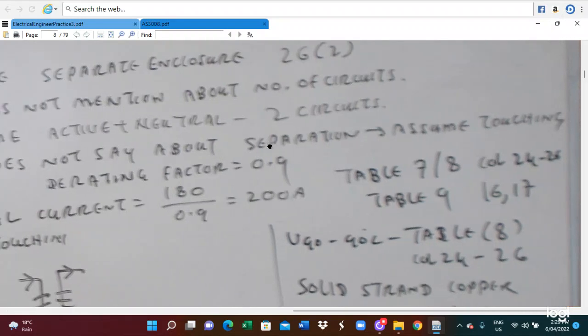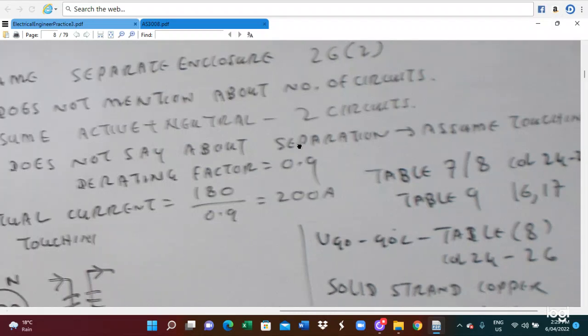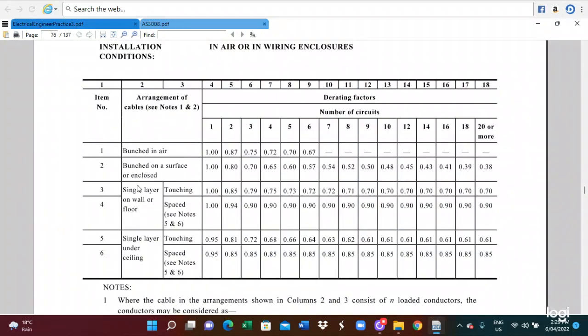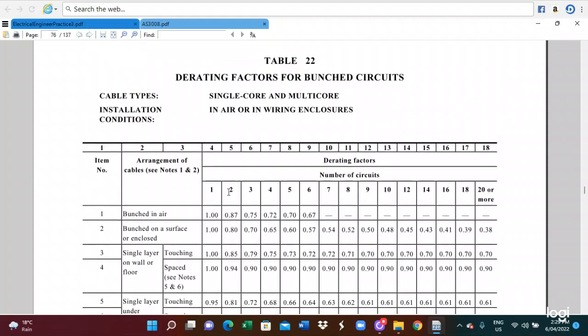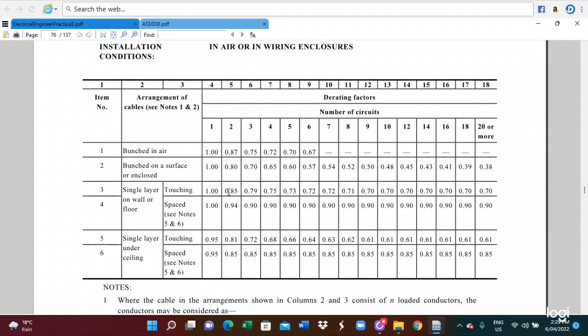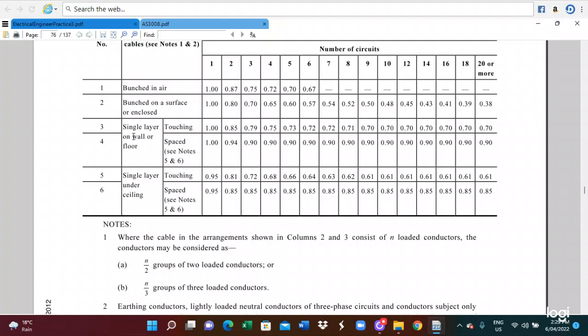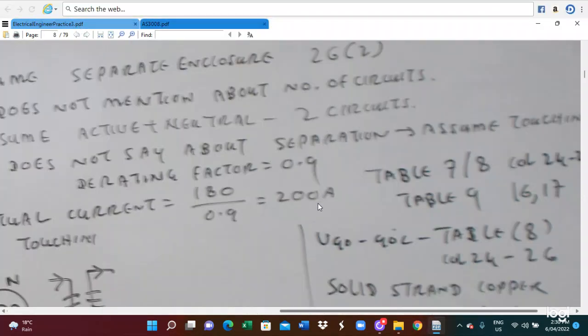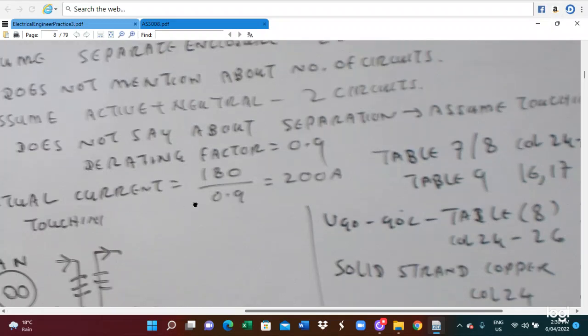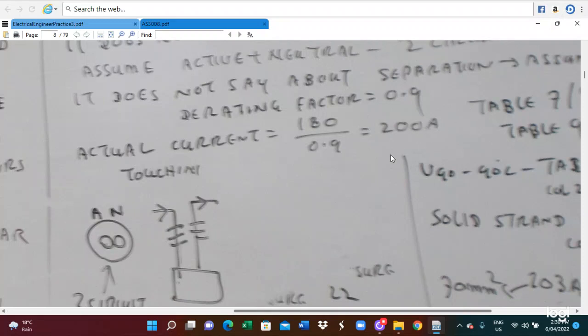It does not say anything about separation, so we assume that the cables are touching. This is touching, single layer touching, so that will be 0.9. You utilize 0.9. So we get 200 ampere: 180 divided by 0.9 gives 200 ampere.